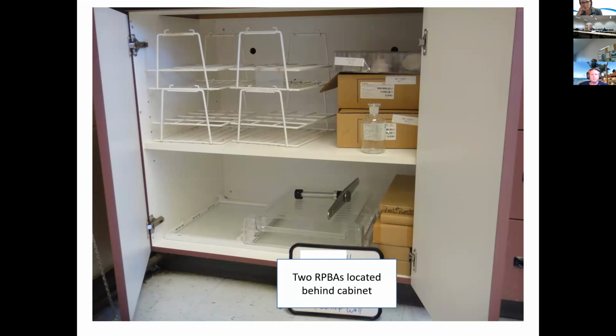So you take all this stuff out, you take the shelf out, you remove that back panel. There are 2 RPBAs back there. And only one person at this lab knew where those backflow assemblies were. It's situations like this where things can get lost. If they start leaking, you're not going to know. You're not going to be doing annual testing if you don't know they exist.